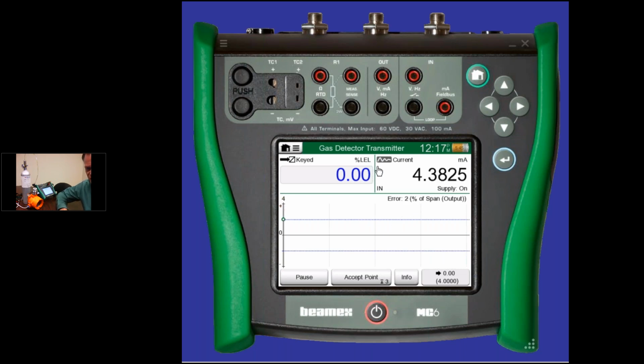And in fact, one of the things Roy talked about, there is a little symbol here on the calibrator. It's just an algorithm that we have, and it's informing you as the technician that this signal's moving. It's not stable. So the calibrator wants to see a nice steady signal, and as it gets slower on the change here, that symbol goes away. So the idea is you can take a recording when this signal is nice and stable. So it's still running down a little bit, but it's looking pretty good. We're pretty close to 4 milliamps. And this signal's getting close enough. So I'm going to go ahead, just for time, and record that reading.